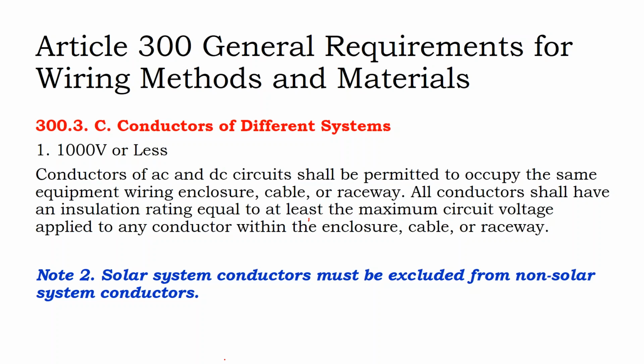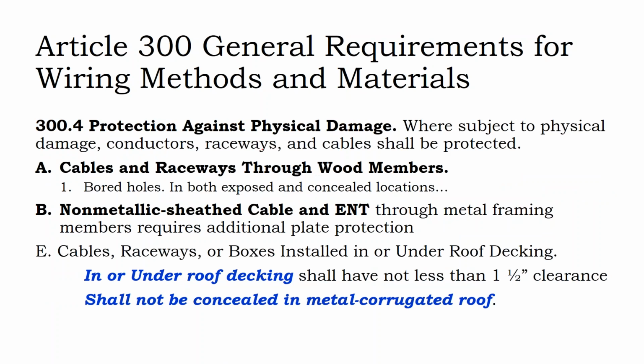And then we also saw that requirement where feeder conductors cannot occupy the same conduit as load conductors. And so we have this informational note that says solar array conductors have to be excluded from non-solar conductors. That informational note will probably change in the future. It'll probably say that on-site distributed power system conductors must be excluded from your load conductors, or just be removed from code as people become more familiar with other sections of it.